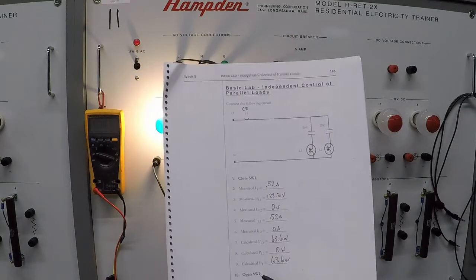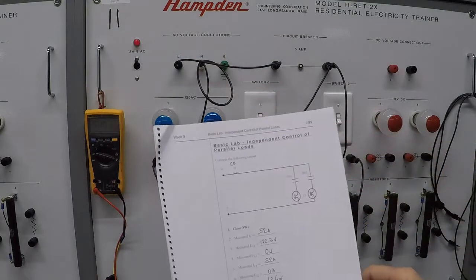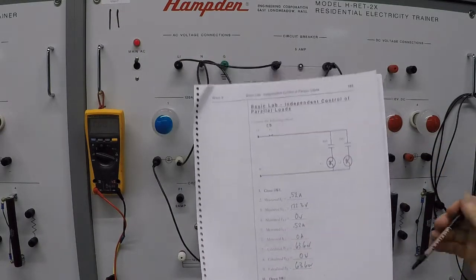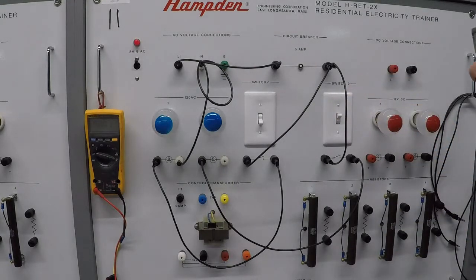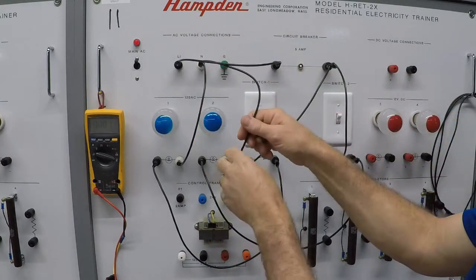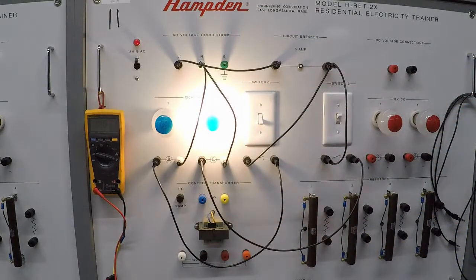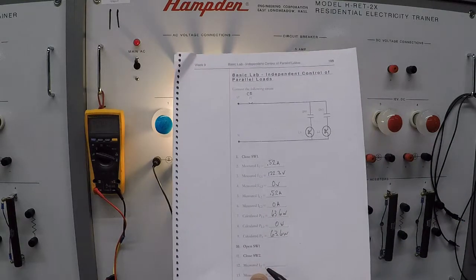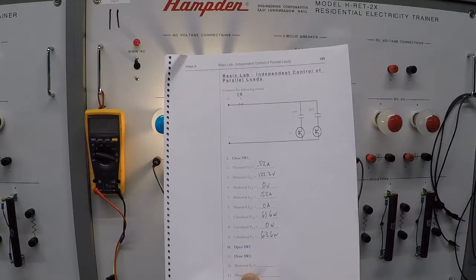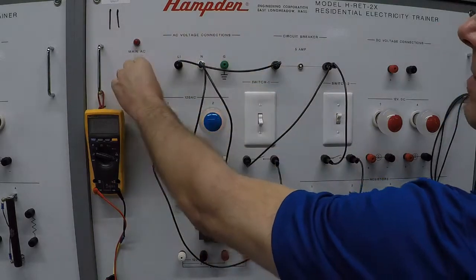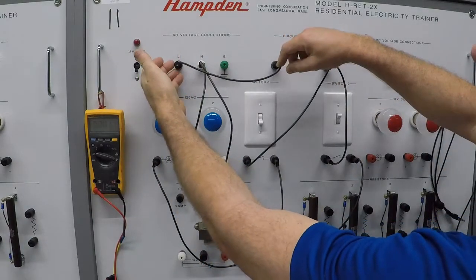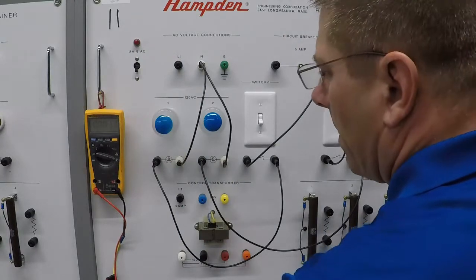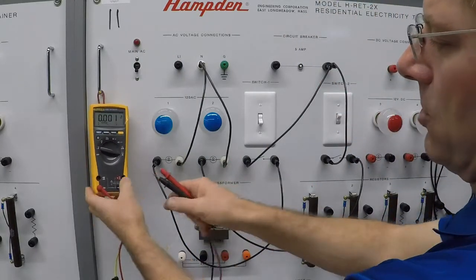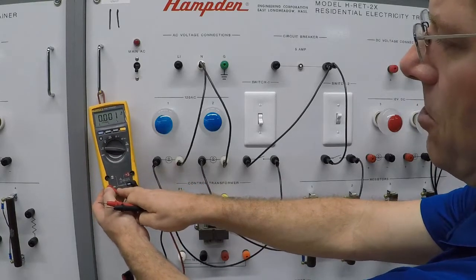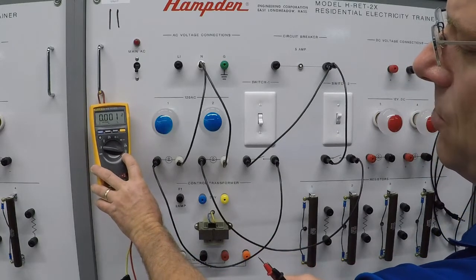Step 10, we open switch 1, so turning that off. Step 11, closing switch 2. We have to reconnect our neutral for it to energize. There, we've powered L2. Step 12 is measuring IT. So we will turn off the main power switch, remove the wire from the L1 to the circuit breaker, place our meter, make sure that your probe connection is correct for current, as well as the setting to AC amps.